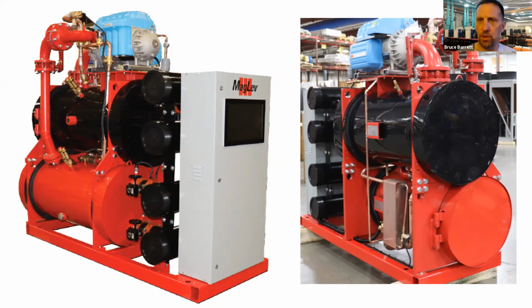The compressors that are shown in this picture are alternative refrigerant. We happen to be showing on this 1234ZE, near zero GWP. We also offer 513A compressors. That's a standard option for us. And of course, 134A is our standard refrigerant right now.